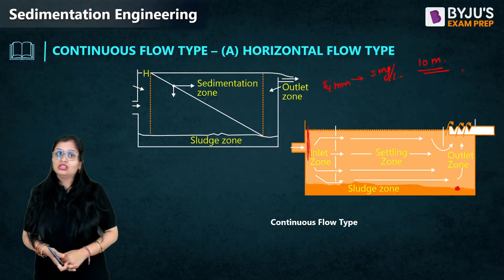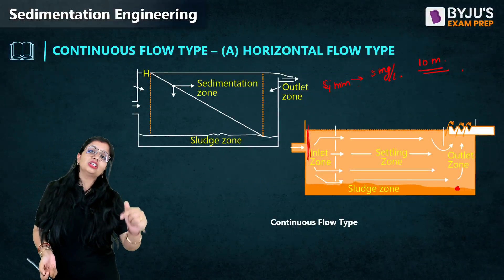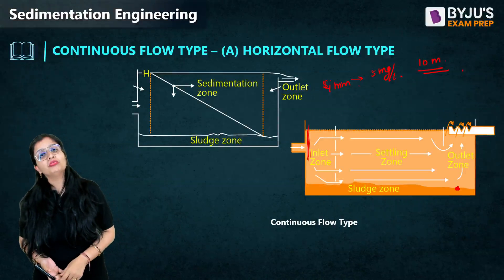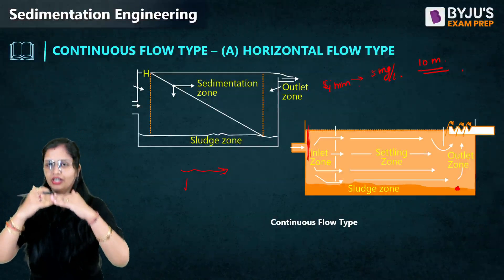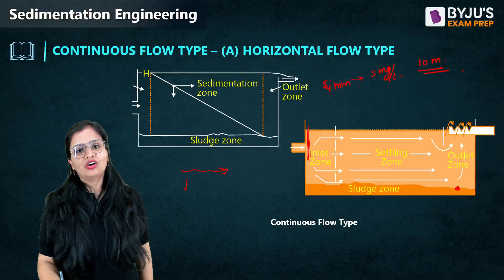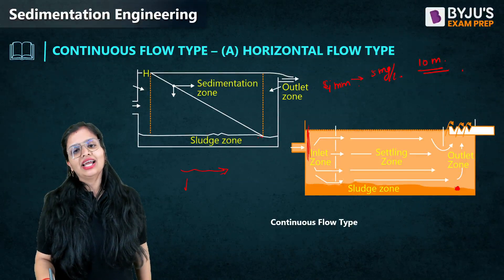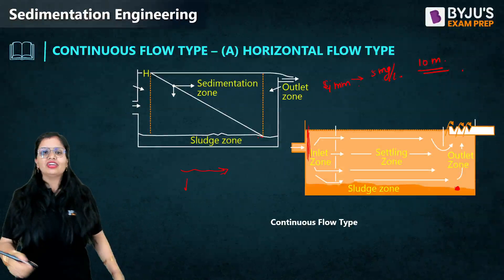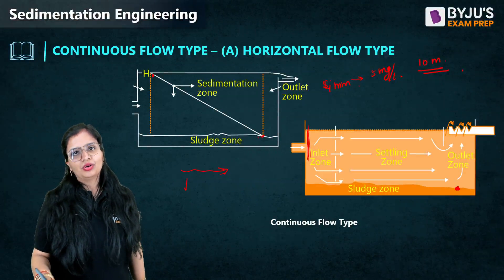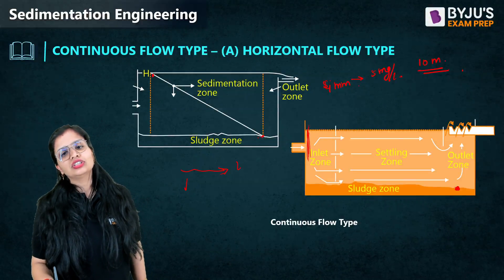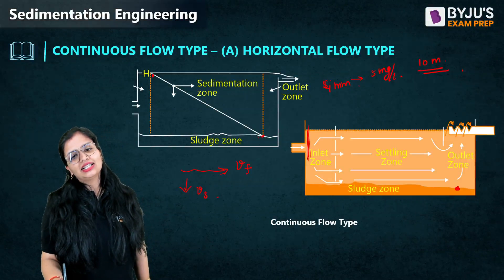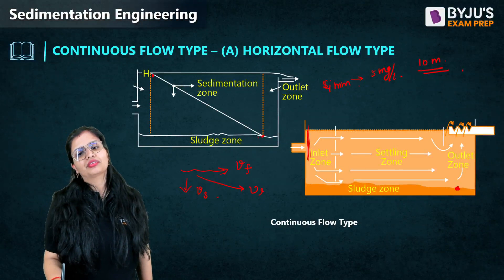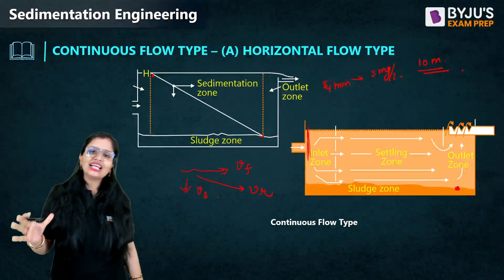The turbulence is not zero, so how is the particle removed? When the particle is traveling forward with the flow, it is also traveling downward due to gravity. So along with the flow velocity in the forward direction, it has a settling velocity in the vertically downward direction — giving a resultant diagonal path. By the time it travels the length of the tank, the particle settles to the bottom.